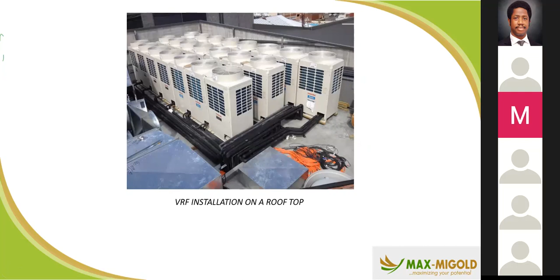You have a section with the two-way valves. If you want to loosen it, you can do so from on top here with a spanner or adjustable spanner on this part. Then you can use your Allen keys to open through this place. This Allen key can actually lock. What does it do? It locks. Sometimes you allow your refrigerant to enter through this way, and you can also discharge through this way.